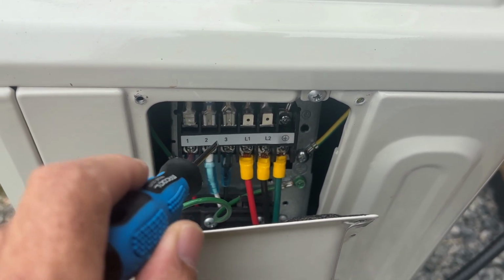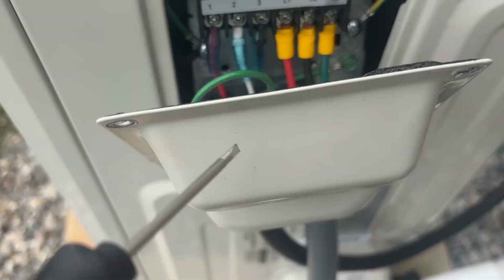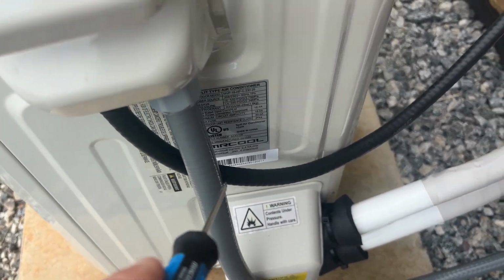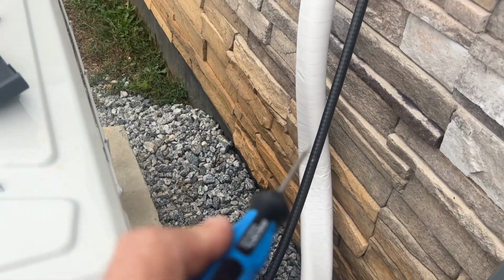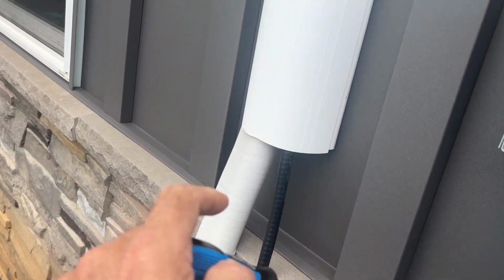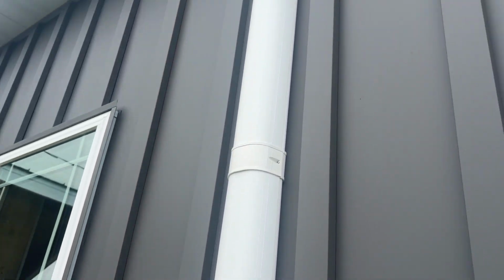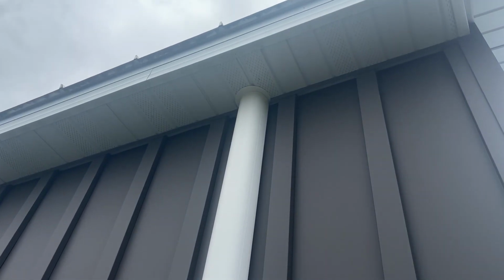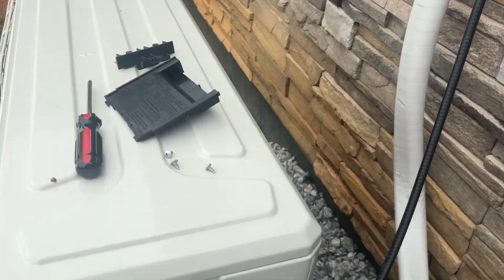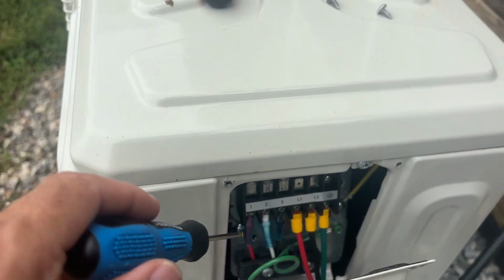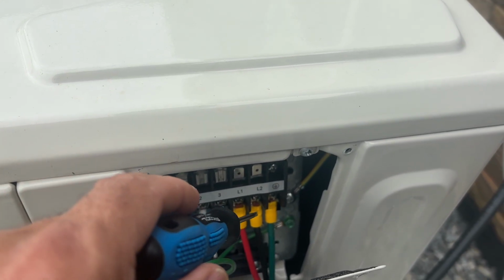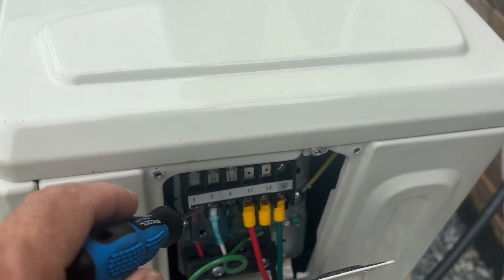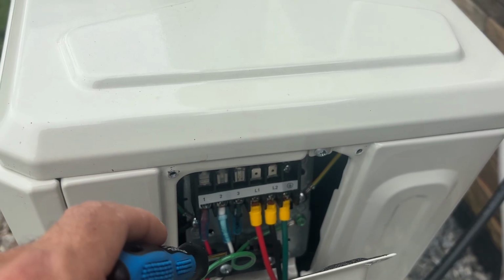You just hook them up as they're labeled, and that goes in this black DIY Pro cable that came with my unit. It's number 14 wire, and it follows the line set up and goes right in the bottom side of my soffit over into the air handler. So this is pretty easy. The book is going to walk you through that, but that's how you get power from your main breaker panel to your outdoor unit, and from the outdoor unit to your indoor air handler. Now let's go inside and look at the air handler hookups.